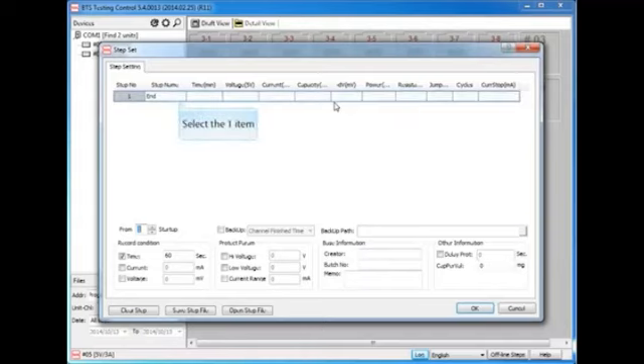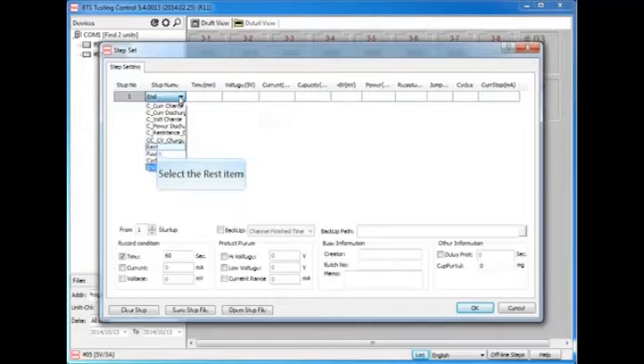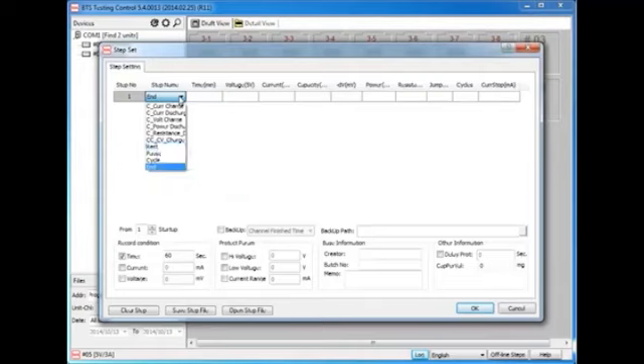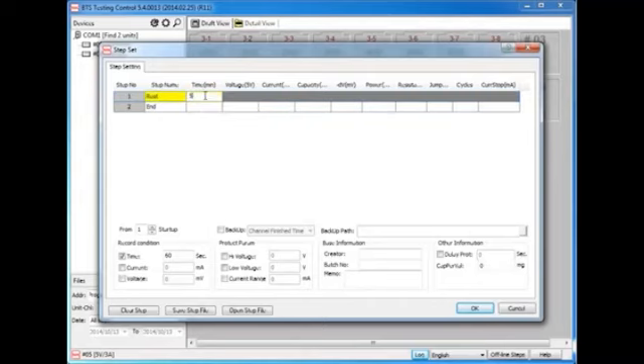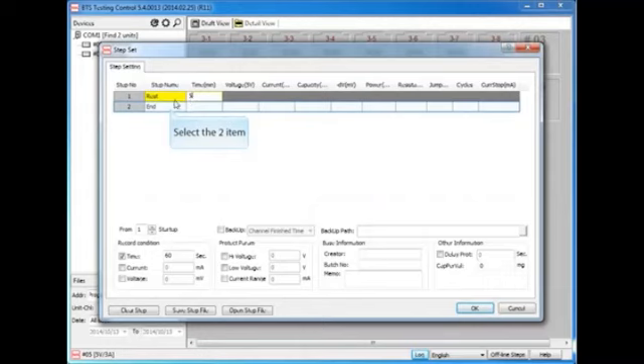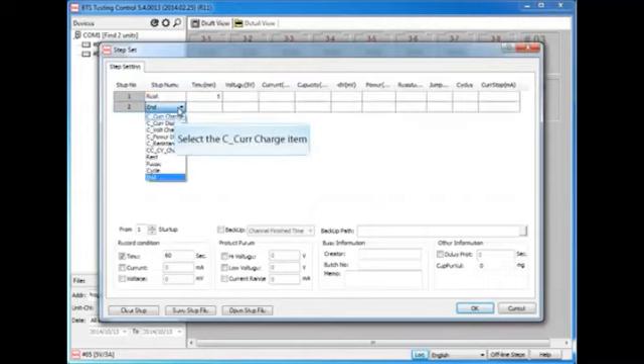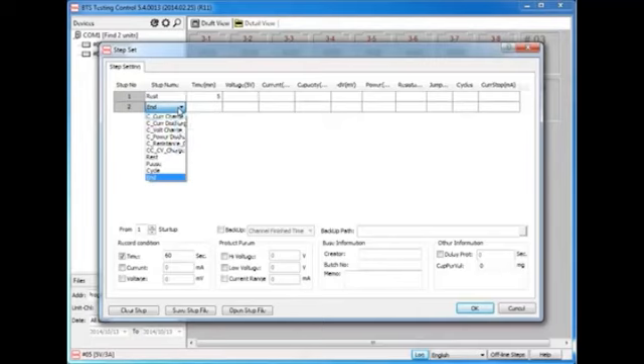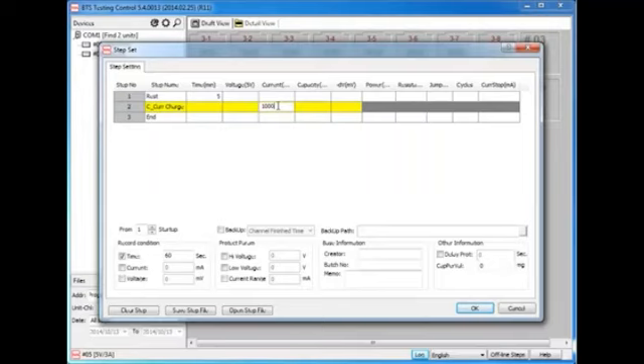Here we made up a typical test as an example. The whole testing process is: Step 1, rest the battery for 5 minutes. Step 2, use constant current to charge the battery until the battery voltage reaches the upper limit.